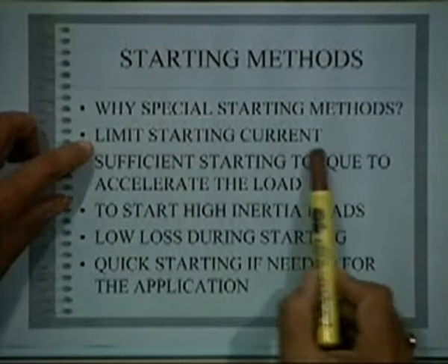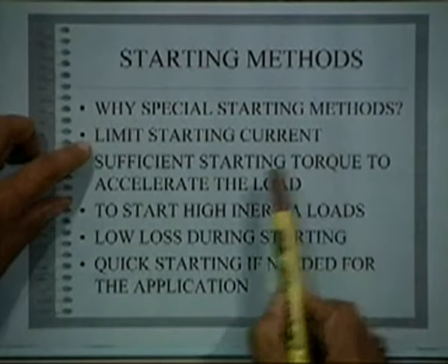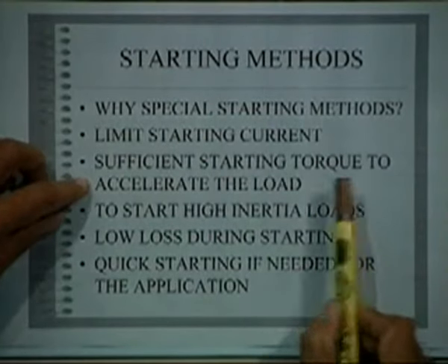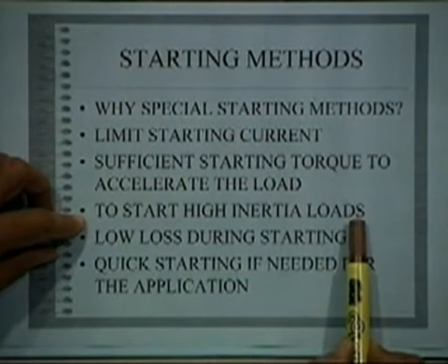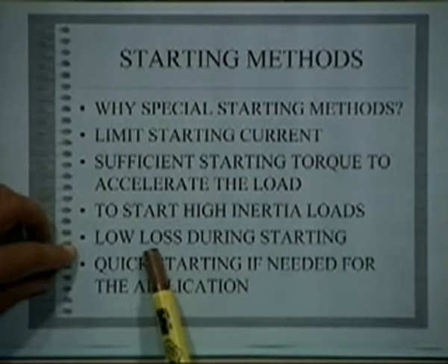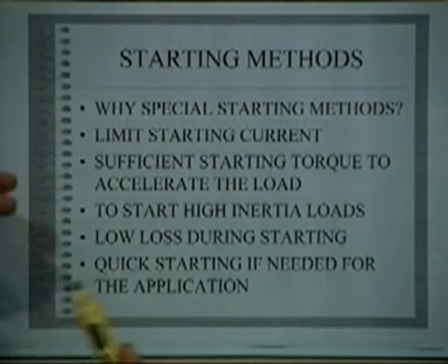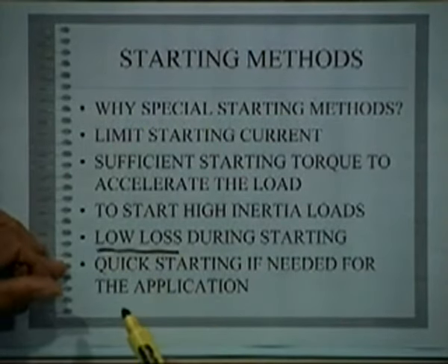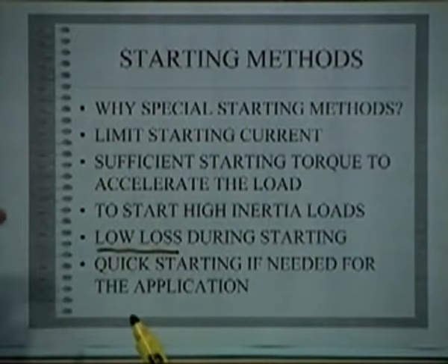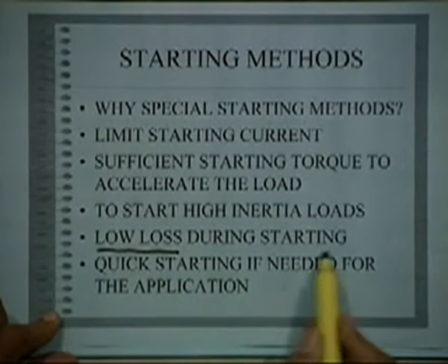So we require good starting current, limited, good starting torque, high inertia loads, and low loss during starting. If it is a high inertia load, it must have low loss, because this is one of the issues of energy conservation. If a load requires several start stops per hour, the motor may get heated, there will be energy loss during starting.